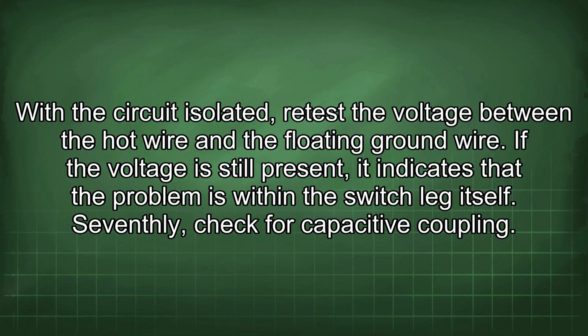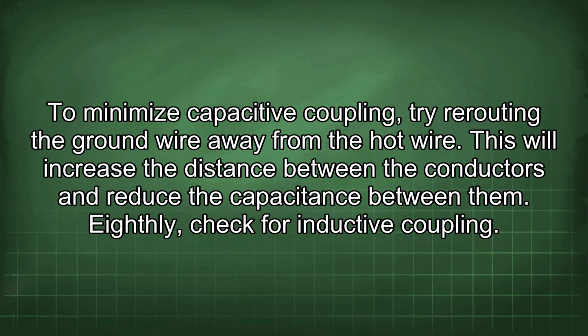Seventhly, check for capacitive coupling. To minimize capacitive coupling, try routing the ground wire away from the hot wire. This will increase the distance between the conductors and reduce the capacitance between them.